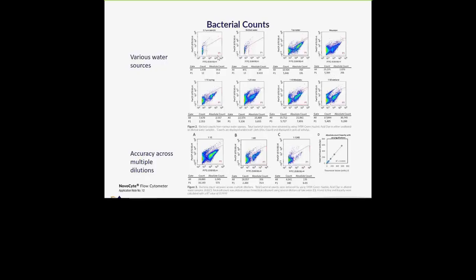With the NovoCyte, which uses a syringe pump that takes up a known exact volume, you can do direct absolute counts without the use of reference beads — saving both time and money. Applying the same gate, you can immediately see all statistics within the software, showing absolute counts ranging from 0.4 to 9,200 cells per microliter across the different water sources. To test the accuracy of the syringe pump, multiple dilutions of the same water sample from 1:10 to 1:1,280 were run, and plotting theoretical values against the NovoCyte absolute counts shows strong linearity, demonstrating the accuracy of the syringe pump.